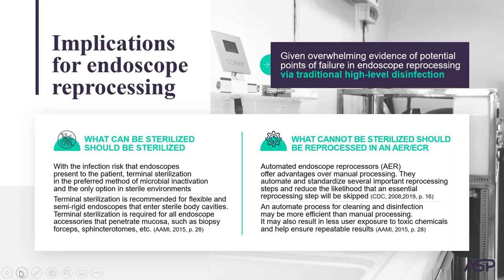What cannot be sterilized should be reprocessed in an advanced endoscope reprocessor, which offers an advantage over manual reprocessing. They automate and standardize several important reprocessing steps and reduce the likelihood that an essential reprocessing step will be skipped. An automated process for cleaning and disinfection may be more efficient than manual processing. It may also result in less user exposure to toxic chemicals and help ensure repeatable results.